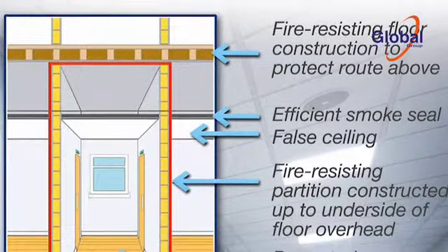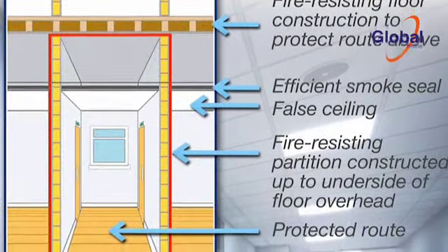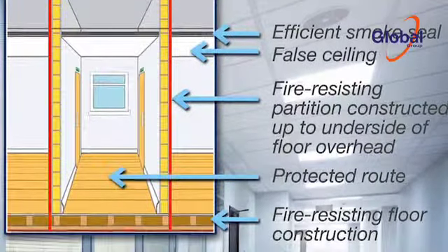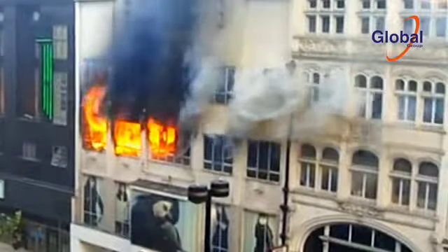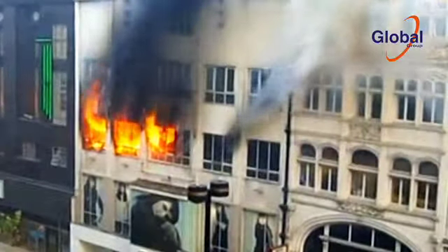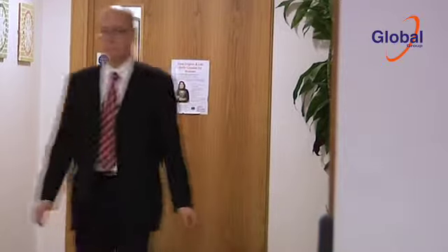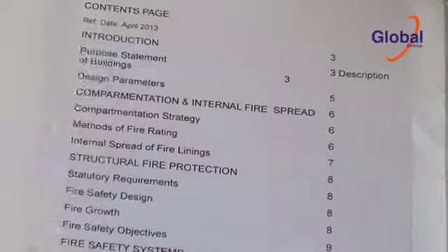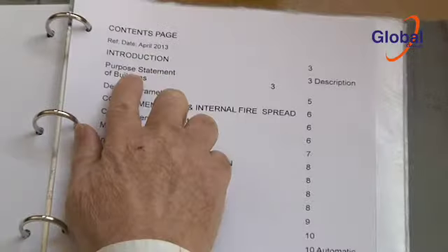These assessments must ensure that any means of escape is not compromised by deficient passive fire protection and that the spread of fire and smoke is restricted. To be able to decide on an appropriate level of passive fire protection, an assessor must familiarise himself with the building layout and escape routes. If the building is relatively new, a fire strategy document may exist, and the information in it may be used in conjunction with the building drawings as a basis for an evaluation.